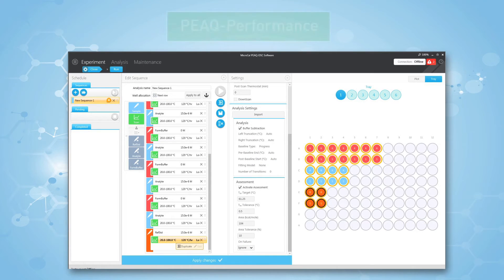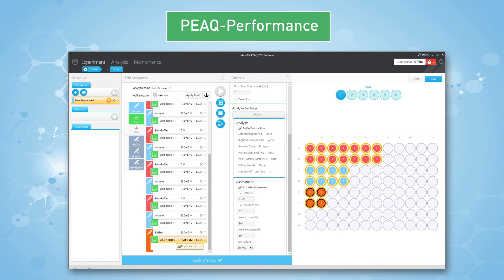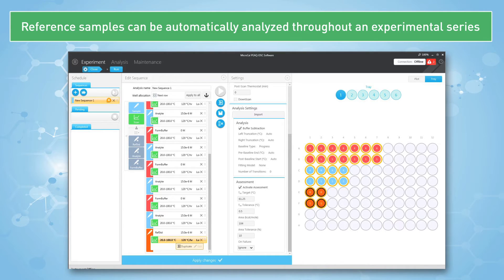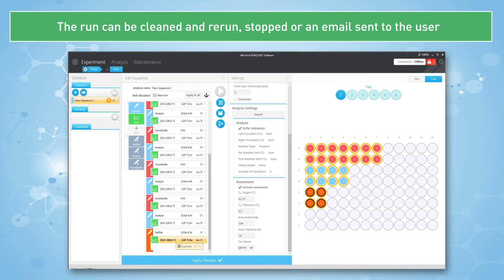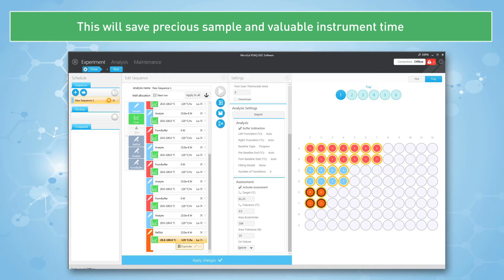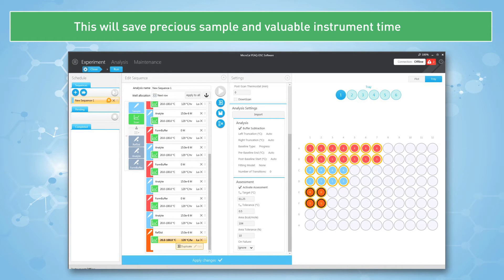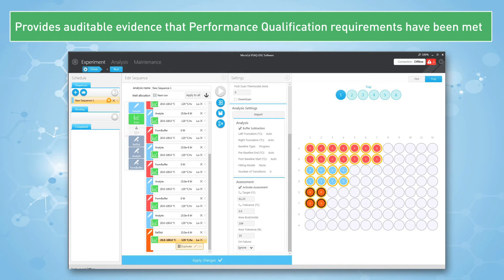The second feature is called PEAQ-Performance. This allows the user to set up reference samples that can be automatically analyzed throughout an experimental series to ensure that the instrument is performing to expectations throughout the entire process. If for any reason performance is sub-optimal, the run can be cleaned and rerun, stopped, and/or an email sent to the user. This will save precious sample and valuable instrument time, and provides auditable evidence that performance qualification requirements have been met.